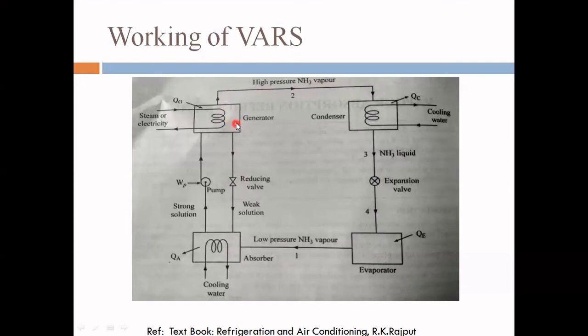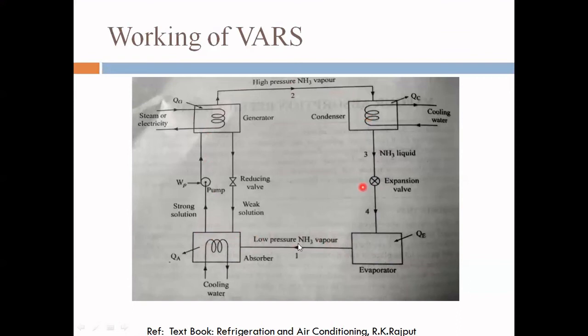Since the generator operates at high pressure and the absorber at low pressure, a pressure reducing valve is needed to reduce the pressure as the weak solution flows from the generator back to the absorber. The weak solution is supplied to the absorber, where the low-pressure NH3 vapor is absorbed by it, converting it back to strong solution, and the whole cycle repeats.